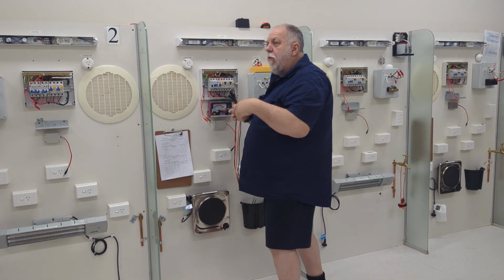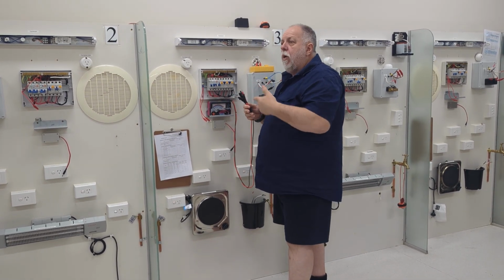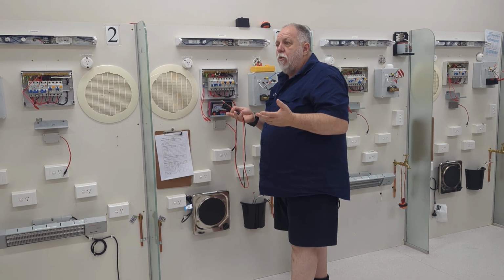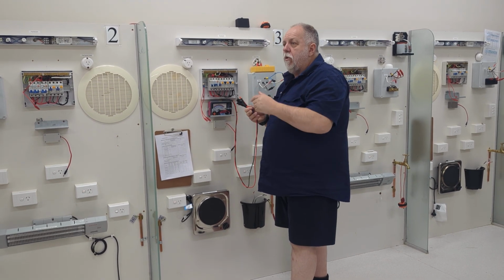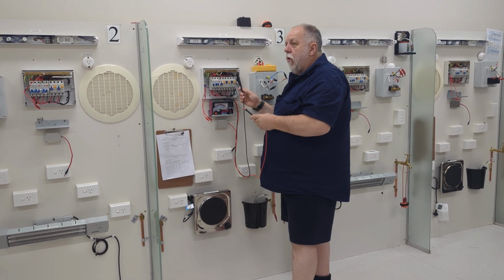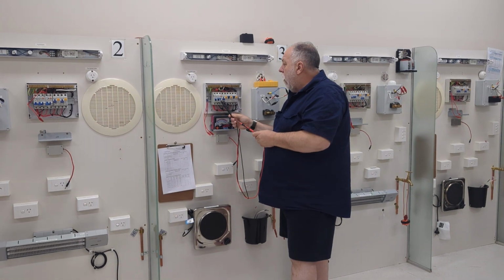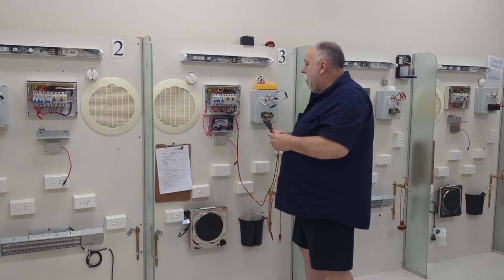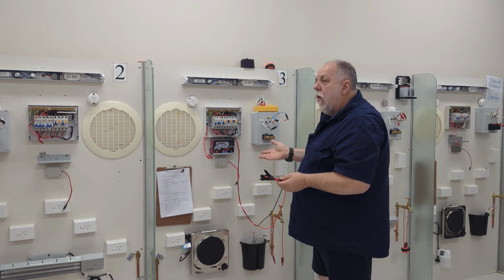Like I said about the twin active before, I have some people go, oh yeah, but I could have a short in the twin active and it could create a short. It's not going to create a short at all. It's still reading between active and neutral to earth. All right, I've done that. I've got my lighting circuit's a problem. Okay, that's all I want to know.